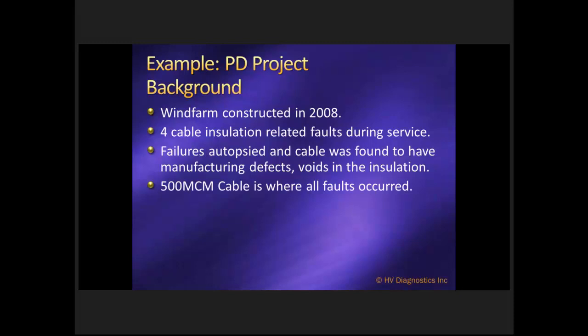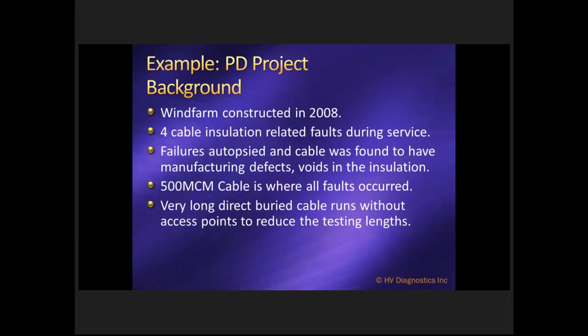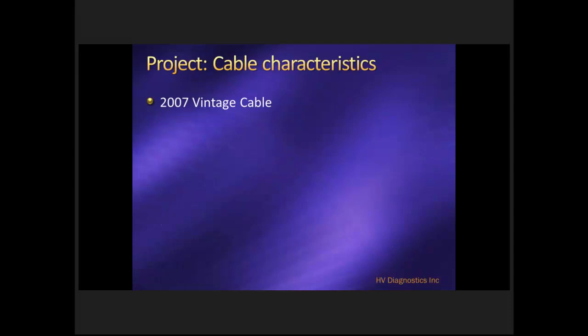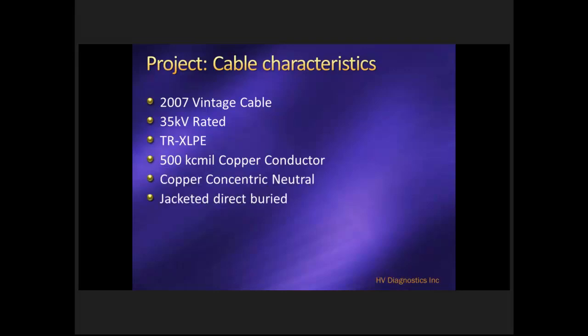All the cables in question were 500 MCM, and these are, at most wind farms, very long direct buried cables with very few points of access to the cable. A 35 kV cable, 10,000 feet long is kind of an average range. Cable characteristics: made in 2007, 35 kV rated, tree retardant cross-linked polyethylene. This is very typical for most wind farms. 500 MCM copper, concentric neutral design, jacketed, direct buried. And the good thing about the cable is that every single site has GPS tags, so it's very nice to go and locate the splices and work.